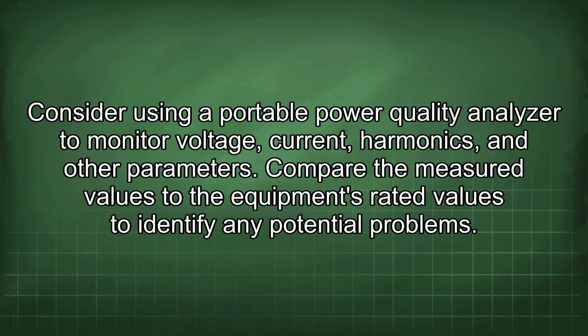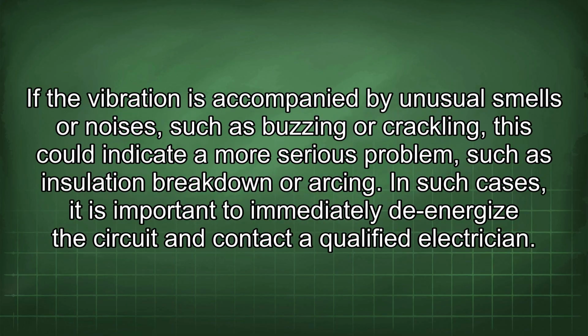Consider using a portable power quality analyzer to monitor voltage, current, harmonics, and other parameters. Compare the measured values to the equipment's rated values to identify any potential problems. If the vibration is accompanied by unusual smells or noises, such as buzzing or crackling, this could indicate a more serious problem, such as insulation breakdown or arcing. In such cases, it is important to immediately de-energize the circuit and contact a qualified electrician.